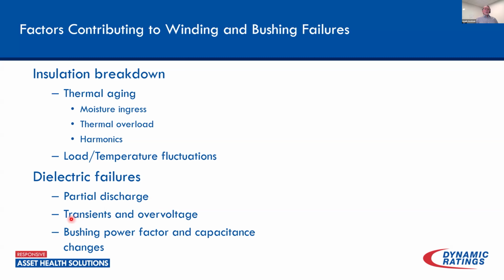It could also be due to transients and overvoltages, switching activity between the vacuum breakers as they're taking the wind turbines and the inverters online and offline. There's a lot of transients and overvoltages there that again could result in dielectric failures within our transformers. And of course, anytime we have those partial discharge transients like that, we could be driving changes in power factor and capacitance, not only in our bushings, but also in the main insulation in the transformer as well.